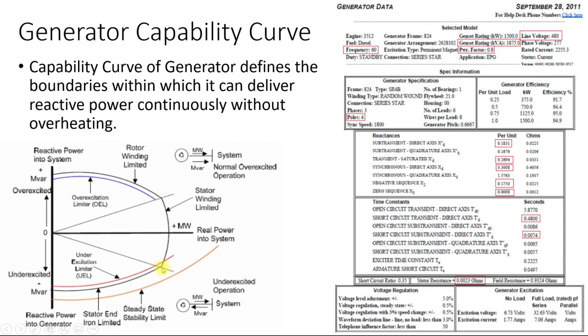The negative range of reactive power provided by the generator is also known as the underexcited range. In the underexcited range, you are reducing your DC current, which reduces your flux. You can reduce the flux up to a certain value, because if you make it zero, loss of excitation will happen. Additionally, weak flux means weak induction on the stator side, which may cause stator heating — that is why there is a lower limit. In the overexcited range, the generator provides reactive power to the system, whereas in the underexcited range, it absorbs reactive power from the system.